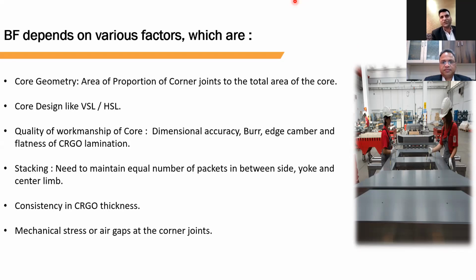Transformer core manufacturers need to check burr at the V-notch stage, the guide hole stage, and the cutting angle stage, because burr at any point means fewer CRGO sheets can be used in the core assembly—since over 1,000 pieces go into a transformer core. If the burr is 0.01 or 0.02 mm, that much space gets occupied by the burr and creates an air gap, reducing the number of laminations needed to achieve the stack height. So burr is a very critical quality parameter that must be controlled.